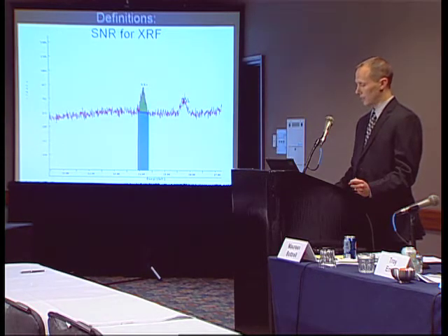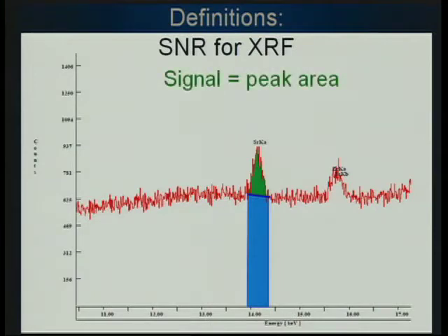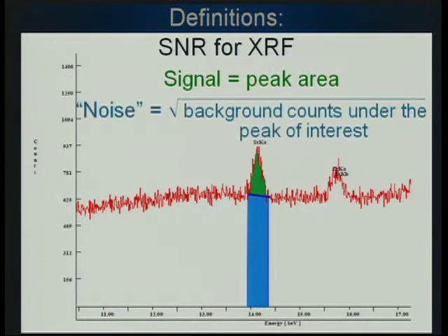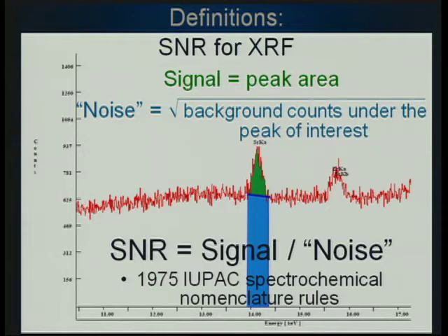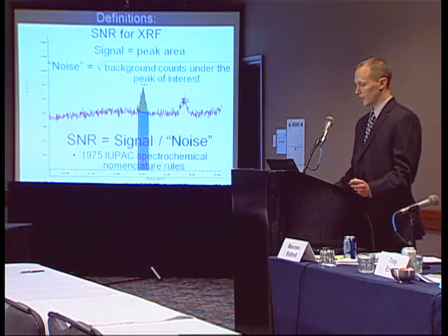The signal-to-noise ratio for XRF is just a little bit different. The signal is still the peak area (shown in green), and the noise is not true noise but rather the square root of the background counts under the peak of interest. SNR is signal divided by this noise. This has been around for a while — it comes from the 1975 IUPAC nomenclature rules — so it's an application of what's already been out there.